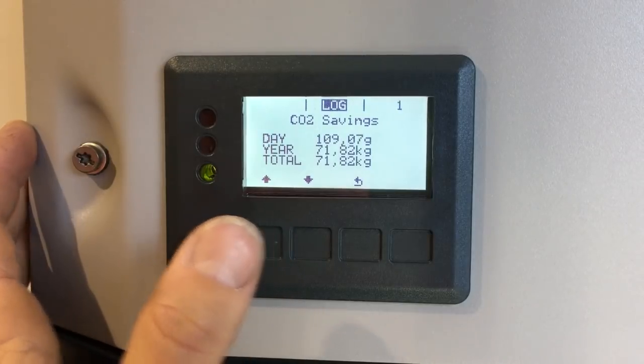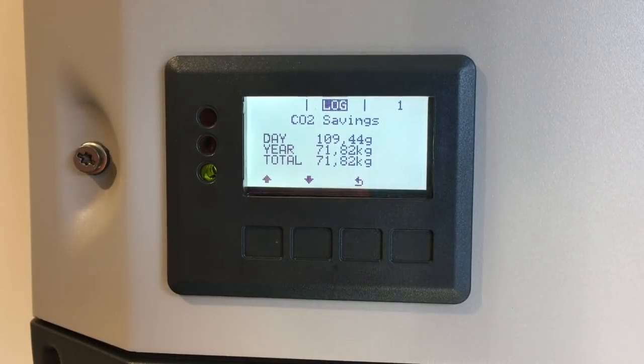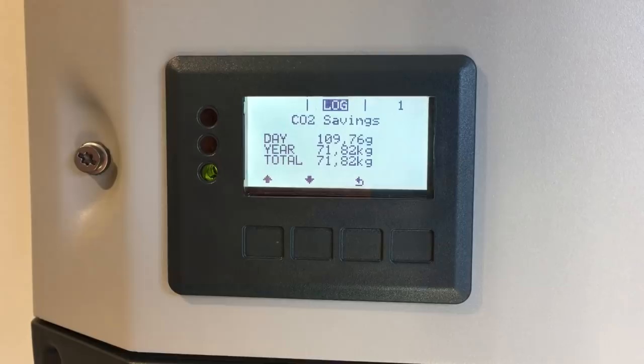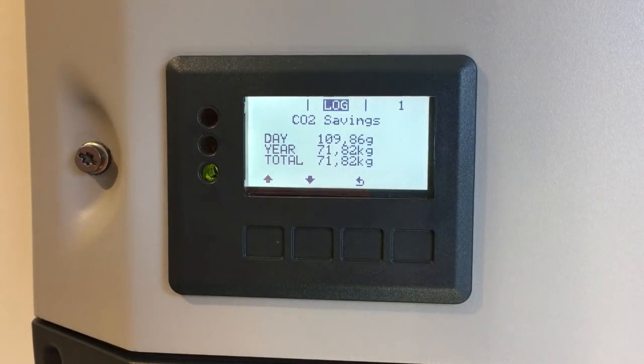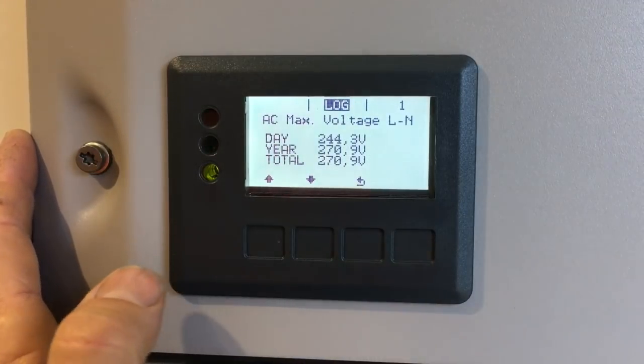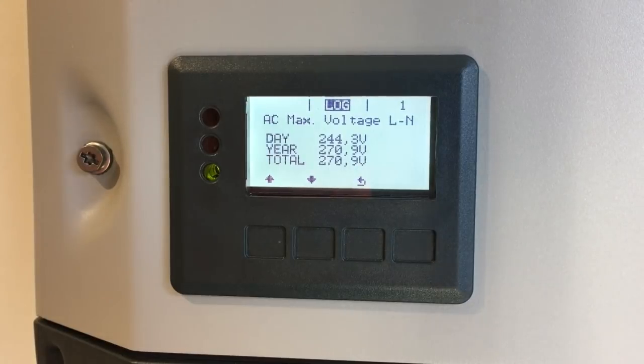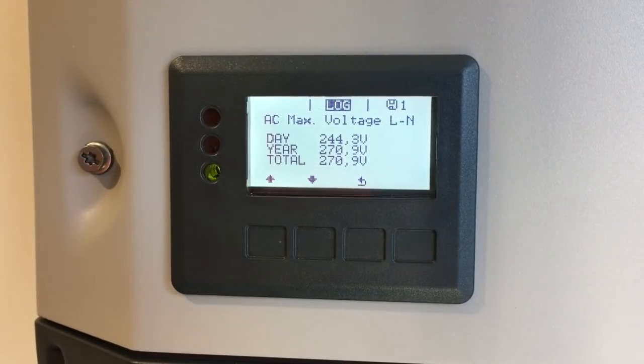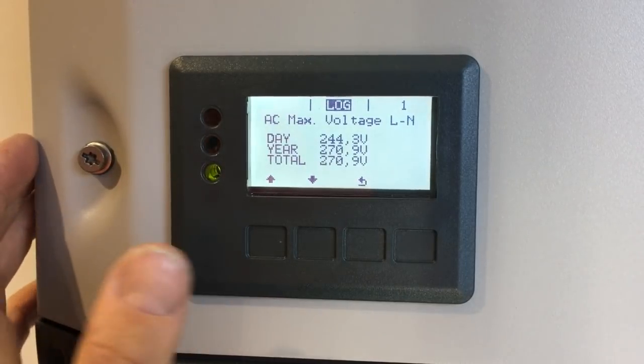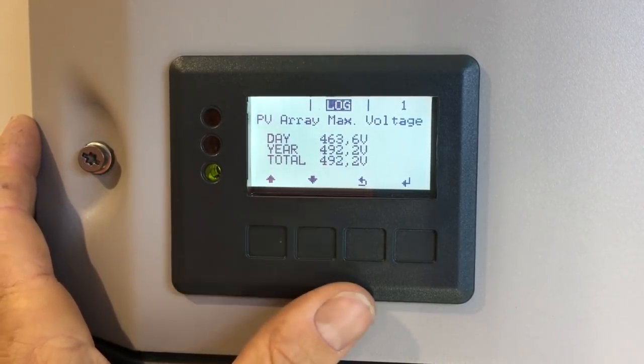You need a smart meter to differentiate what rate the solar is actually saving you. Next is carbon dioxide savings — comparing solar generation to a coal-fired power station, since solar has zero CO2 emissions. Then AC maximum voltage, showing the highest grid-side voltage the inverter has seen today, in the last year, and since installation. If the yearly figure is very high consistently, there may be a major problem. Scrolling further shows PV array maximum voltage.